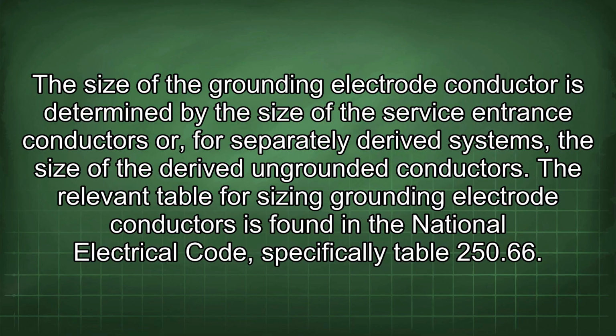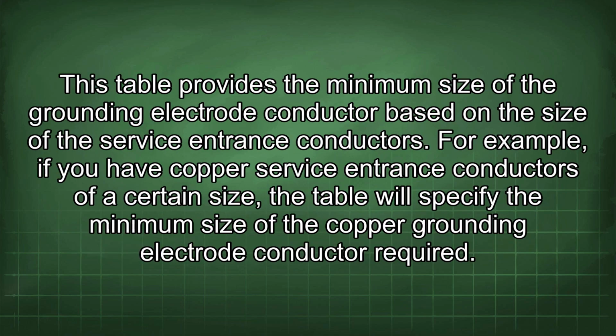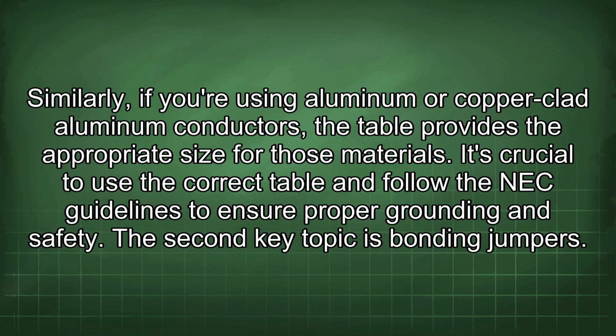The relevant table for sizing grounding electrode conductors is found in the National Electrical Code, specifically Table 250.66. This table provides the minimum size of the grounding electrode conductor based on the size of the service entrance conductors. For example, if you have copper service entrance conductors of a certain size, the table will specify the minimum size of the copper grounding electrode conductor required. Similarly, if you are using aluminum or copper-clad aluminum conductors, the table provides the appropriate size for those materials. It's crucial to use the correct table and follow the NEC guidelines to ensure proper grounding and safety.